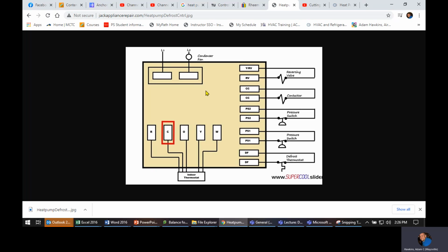So this board has both. This board has low voltage and high voltage on it. So high voltage wires coming in to that board. So if you went to change this board, for example, you needed to change it out, you're going to have to kill the indoor unit to kill the 24 volts. You're going to have to kill the outdoor unit to kill the high voltage. So do both, because you'll blow something, you'll burn something up, or get shocked, or both. So that's just basically breaking one leg to the condenser fan.